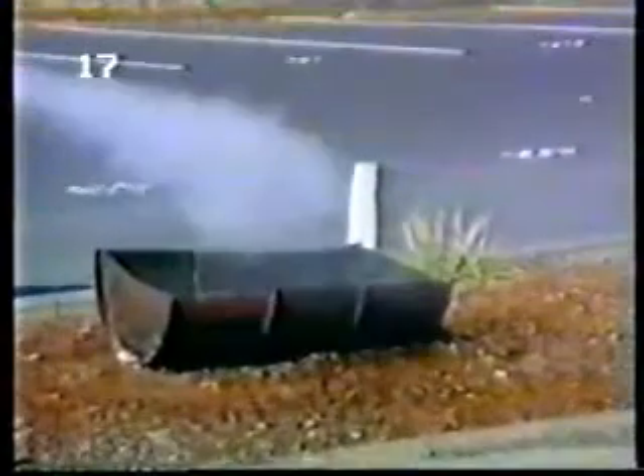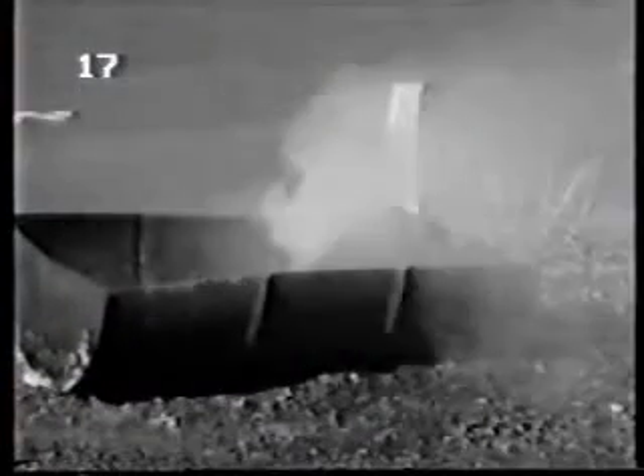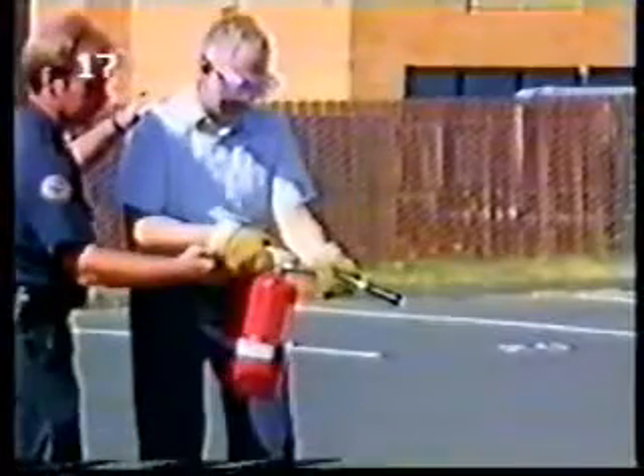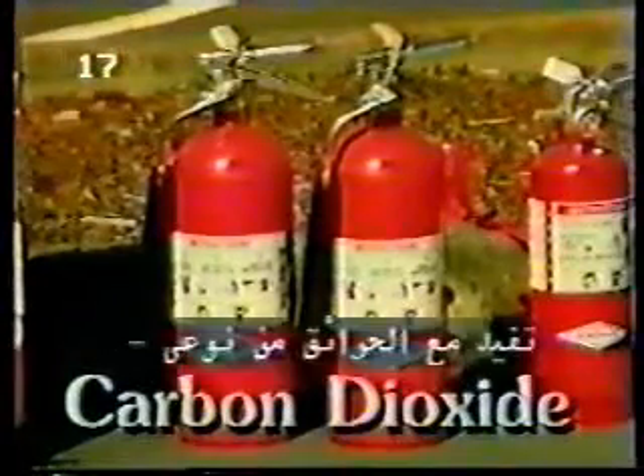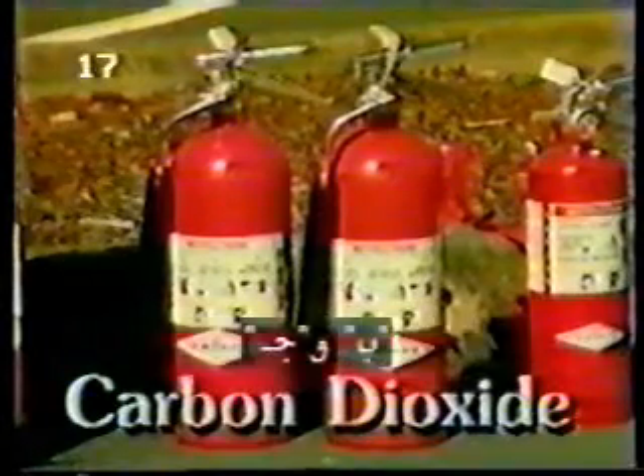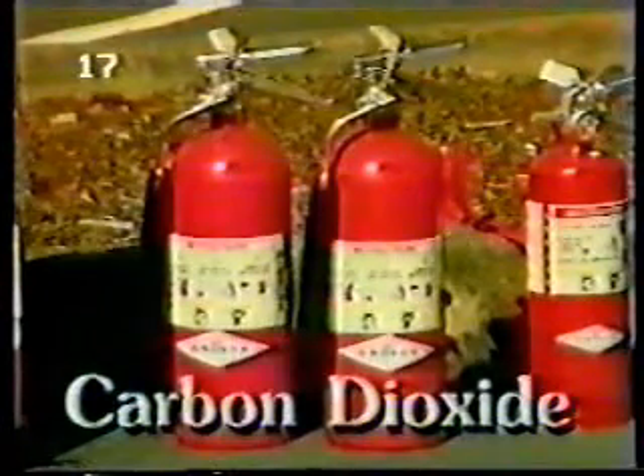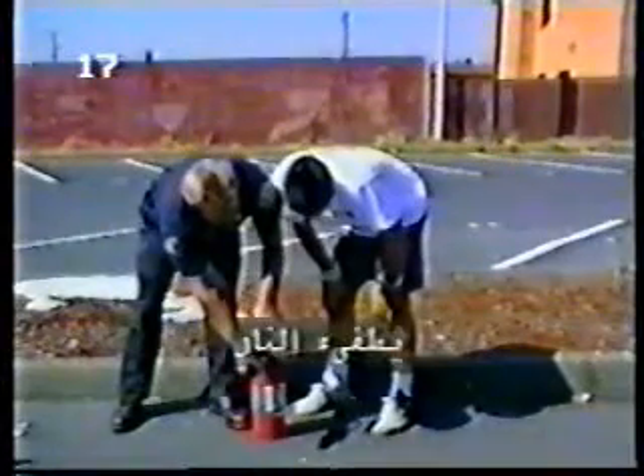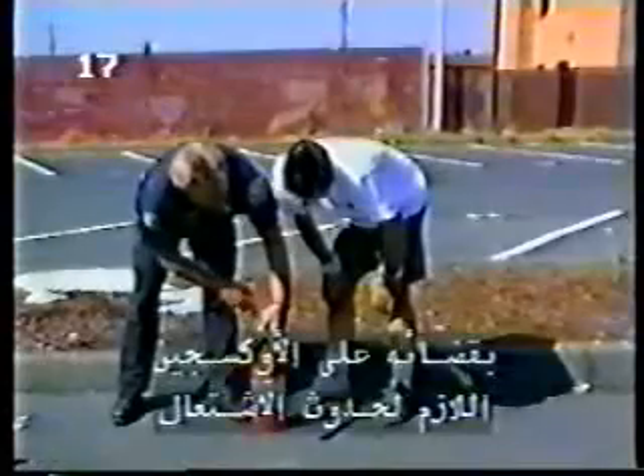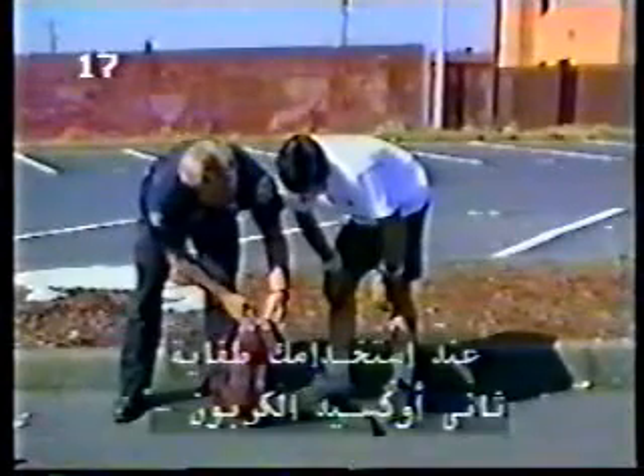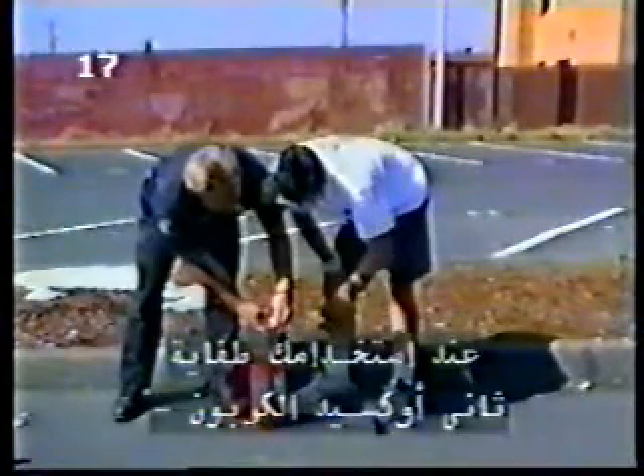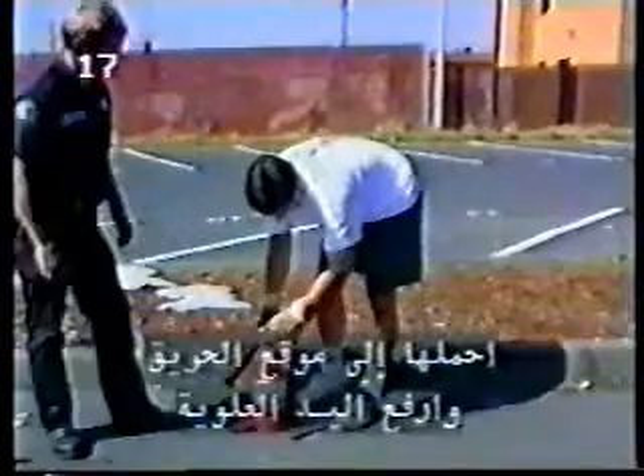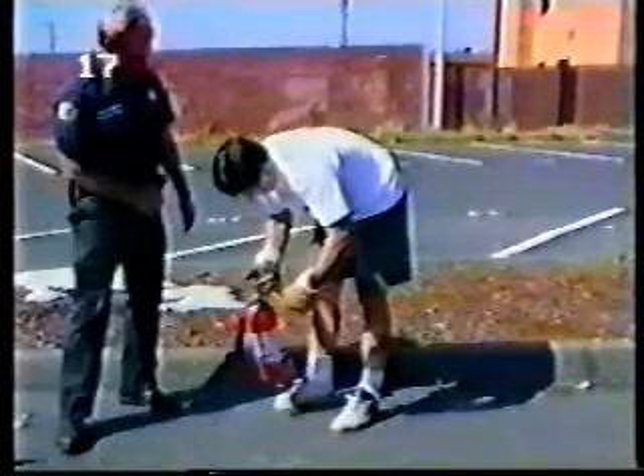Be aware that CO2 extinguishers are very loud when they expel the agent. Also, keep your hands on the handle in back of the discharge horn because the discharge is very cold and can cause freeze burns. On flammable liquid fires, it is best to sweep the flame from the burning surface, starting at the near edge of the fire and moving forward. Continue to apply the discharge after the flames are extinguished to prevent a reflash.